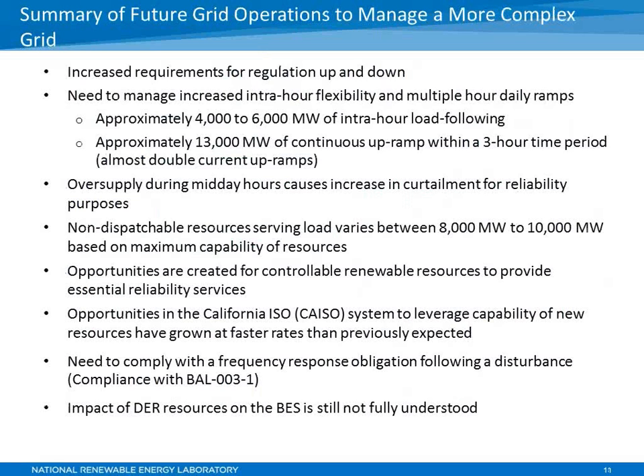We balance the system on two time frames in real time. Every five minutes, we balance the grid based on economics, forecasting what the system will need and dispatching the most economic units in state and what we can get on the ties to meet load demand. Then every four seconds, we dispatch regulation to meet the intra-five-minute variability on the system.